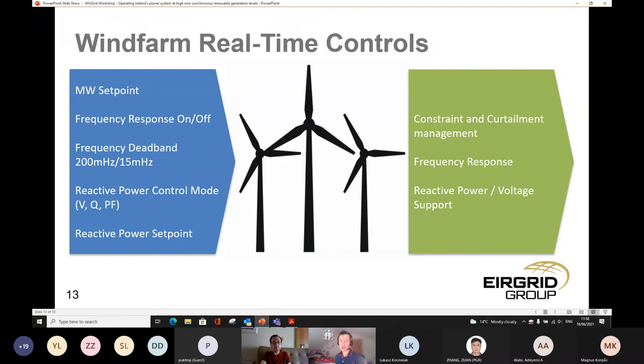And on the frequency response, generally frequency response remains on the wind farms, and what changes occasionally is the dead band. In normal conditions, the 200 millihertz dead band is applied. Predominantly we're trying to maximize the amount of wind being produced, so we don't want it downward regulating.